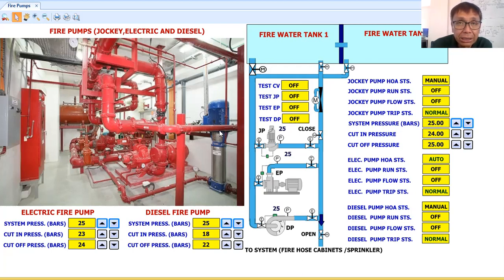Now guys, NFPA 20 is the one that will give the regulation on how you are going to install, what are the requirements for stationary fire pumps, okay. So NFPA 20 will be the one to handle this, okay. Now here, let me simulate. I will try to drop the pressure, okay. Now 1 bar. So my cut-in pressure is 24 bars, as I have shown it here.